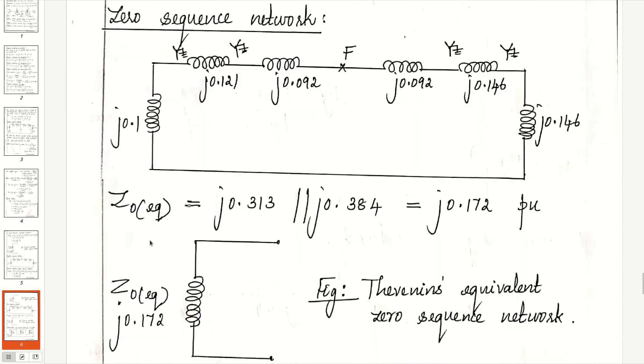For the zero sequence network, use the X0 new per unit values of all components and note the transformer configuration and grounding of the generator and motor neutral points. Both sides of both transformers and the machine neutrals are solidly grounded, so the series switches are closed — no delta configuration. The series combination of 3 reactances in parallel with the series combination of 3 more reactances gives Z0 equivalent as j0.172 per unit. The Thevenin's equivalent zero sequence network consists of only Z0 equivalent.